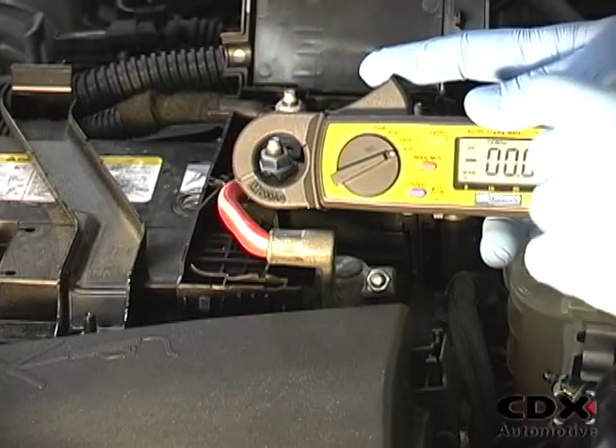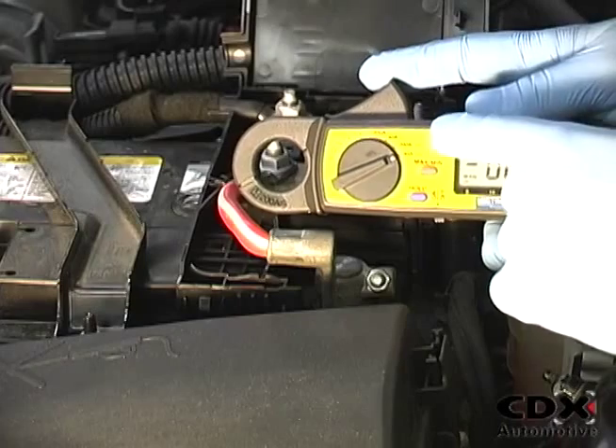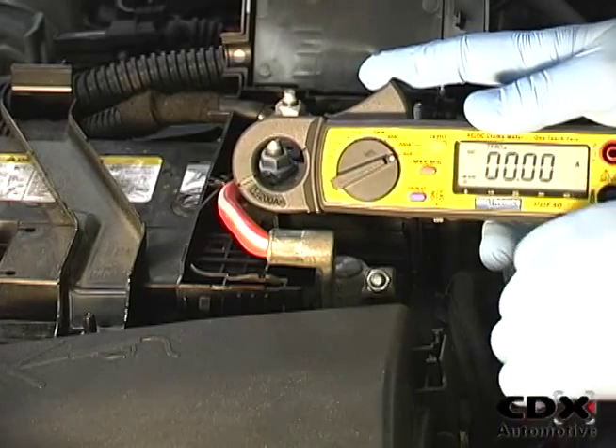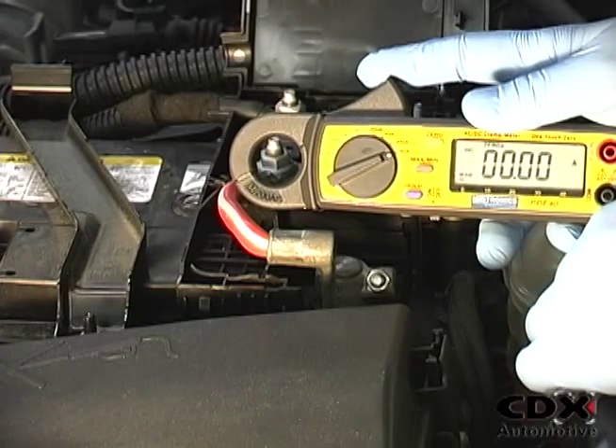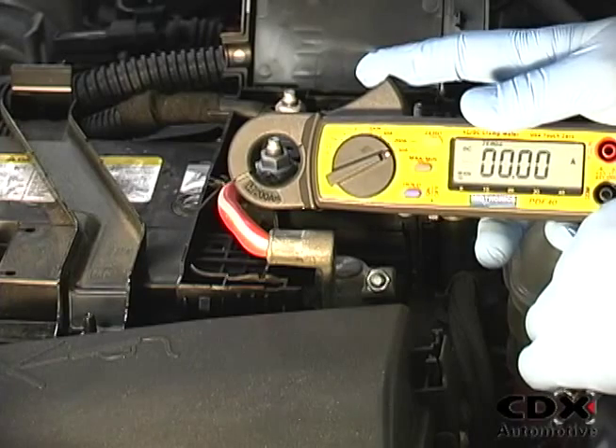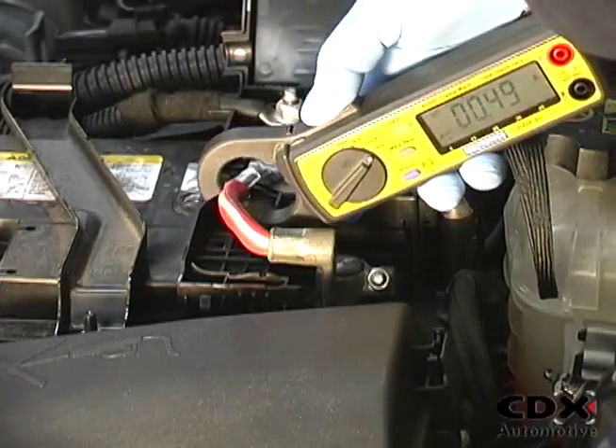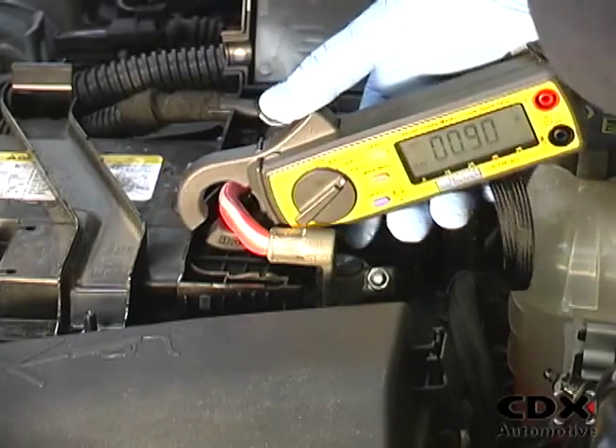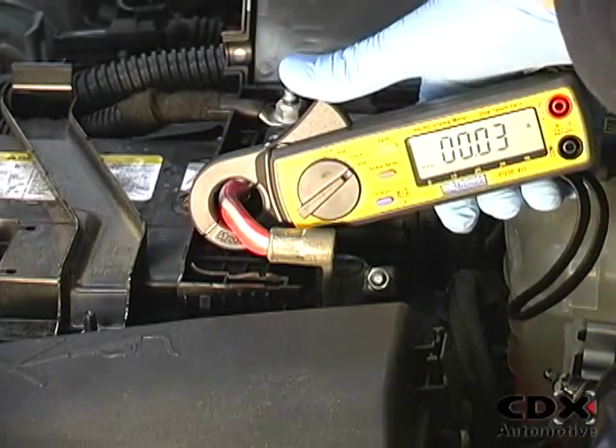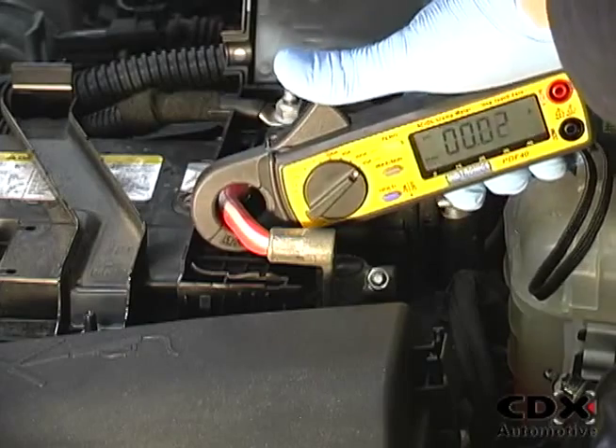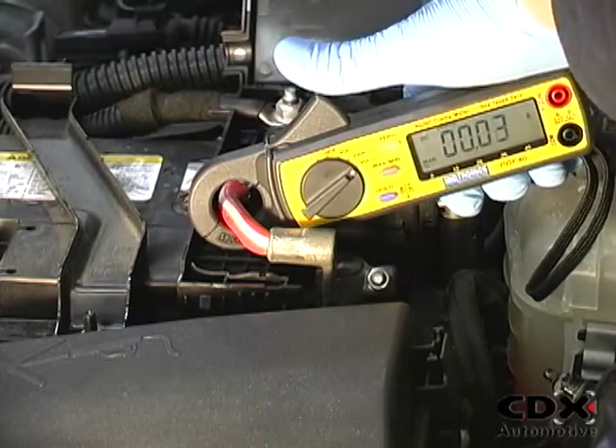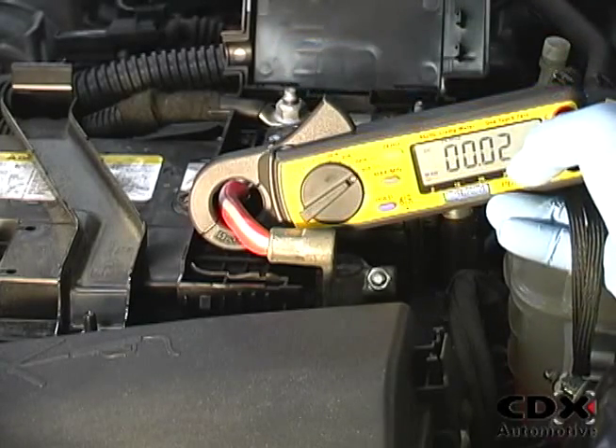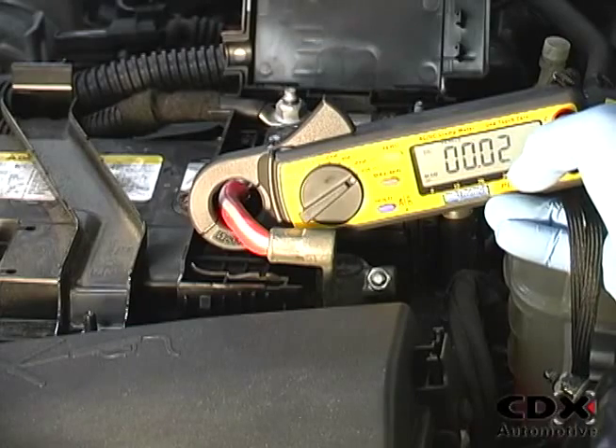Place the inductive clamp meter next to the battery cable and zero the meter again. Inductive clamp meters will tend to drift over time, so the meter needs to be re-zeroed periodically. Place the inductive clamp meter around the battery cable and make sure that it closes completely. Open and close it several times to make sure that it's fully closed. Confirm that your reading is within specification.